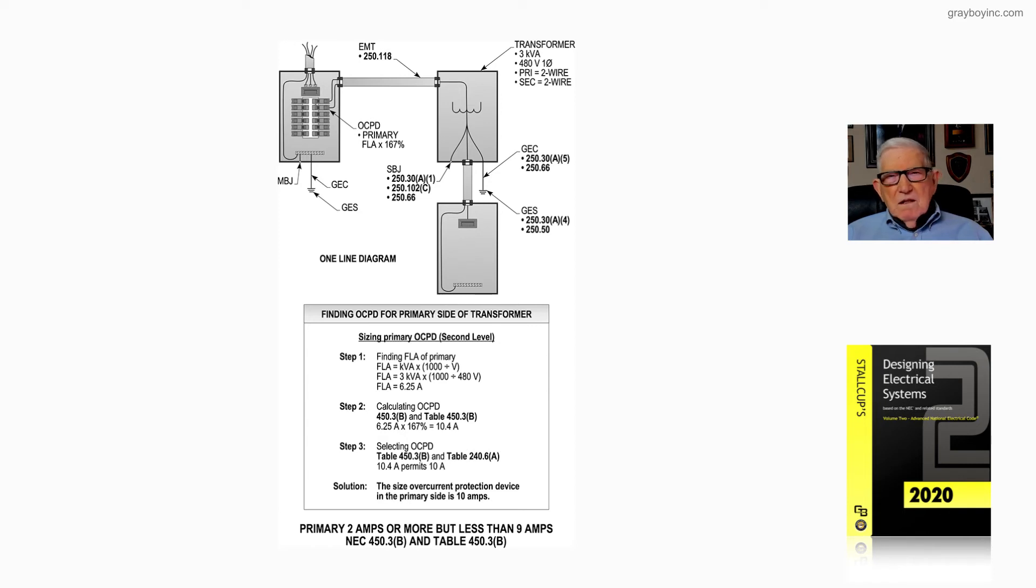The grounding electrode conductor is sized again from 250.30A5, 250.66, as well as table 250.66 if you should connect it to the structural steel. And then of course you select the grounding electrode from 250.30A4 and 250.50 of the code if there's more than one electrode.